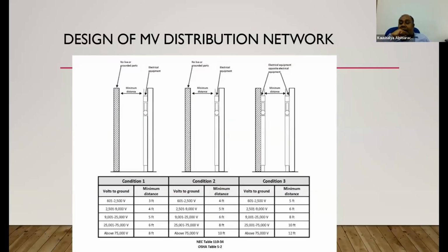This is what is demonstrated by NEC standards or OSHA's, American. So there are three conditions that they discuss. Condition 1: medium voltage switchgear enclosed in a metal enclosure? If so, that falls under condition 1. Condition 2: medium voltage switchgear, open type, with exposed parts grounded. Condition 3: two medium voltage switchgears, open parts grounded.